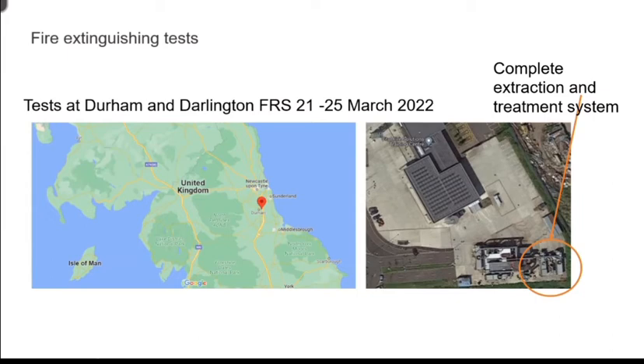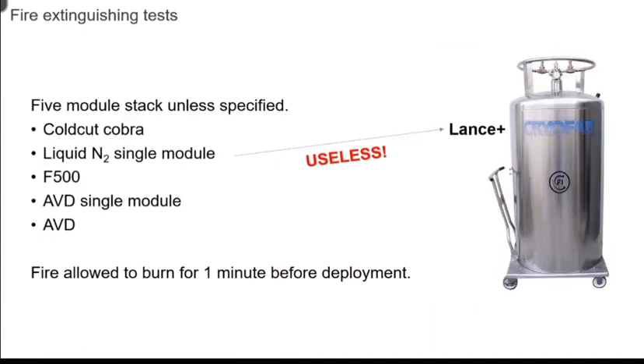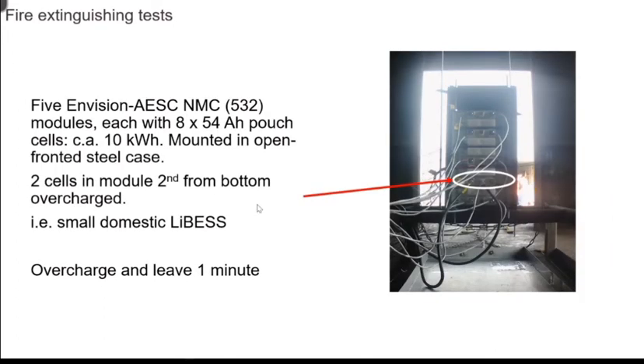But the key point here was that Cold Cut Cobra prevented thermal propagation, but it took a fair amount of time, about a minute and a half, despite the fact that the operator, the fire officer, knew which module we were overcharging, the second from bottom one. It did stop thermal propagation to the top 3 modules. Those 2 went, but he had to keep moving it around.